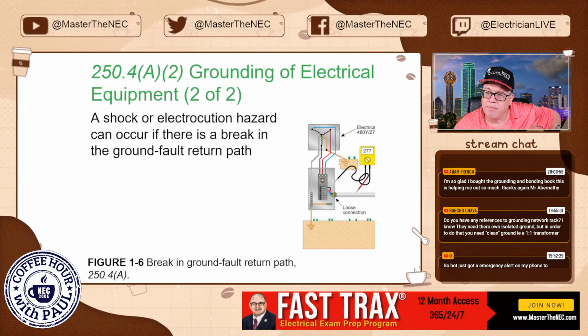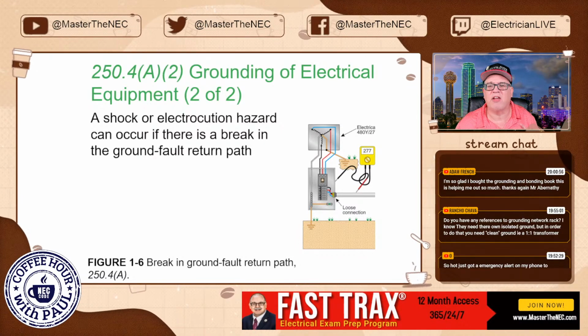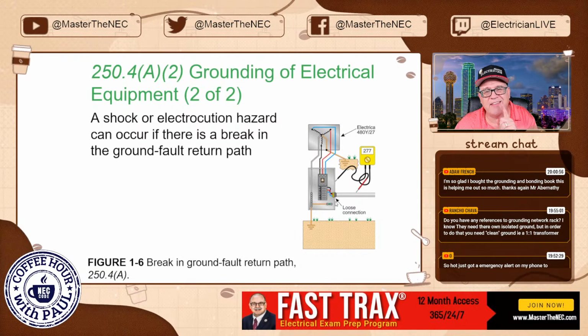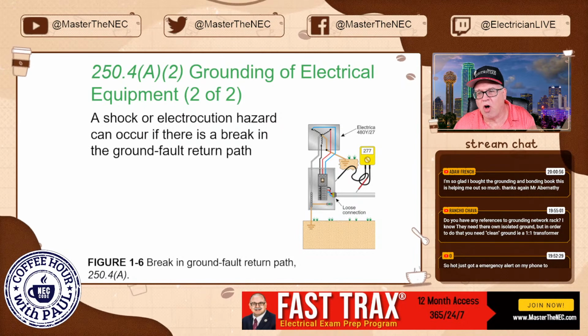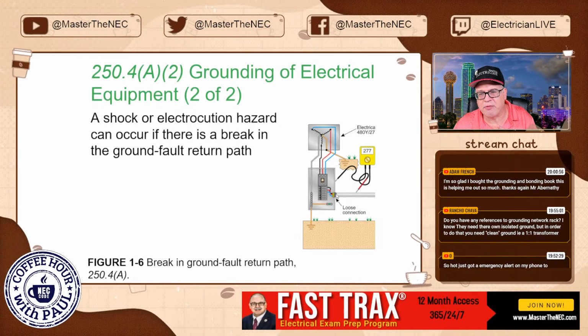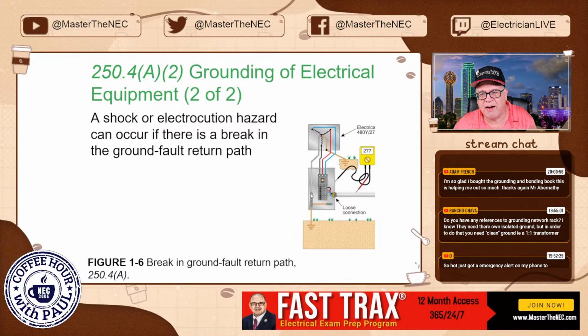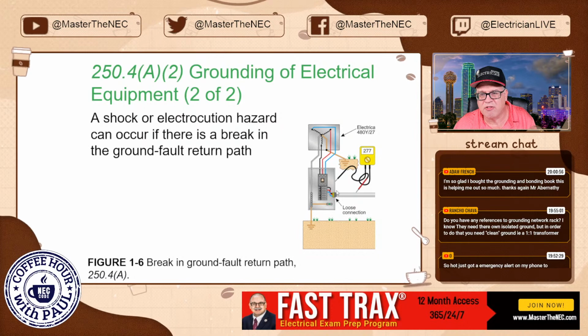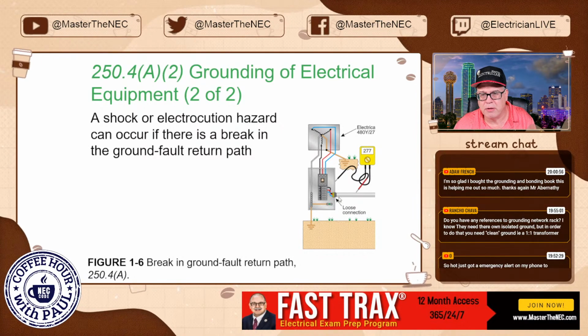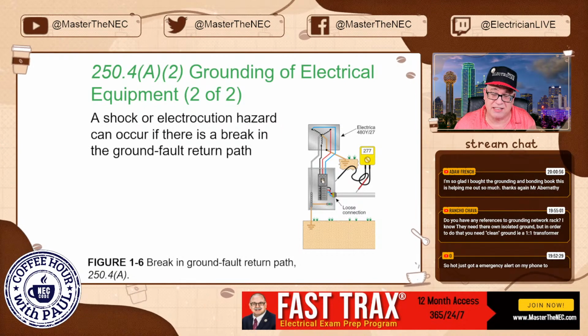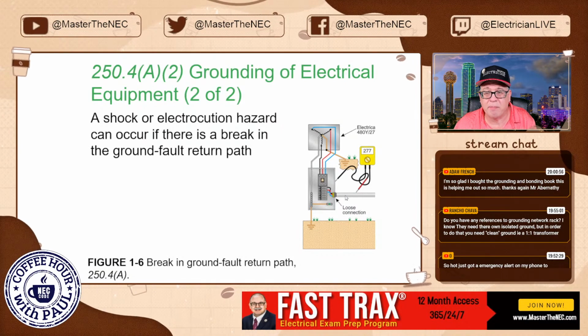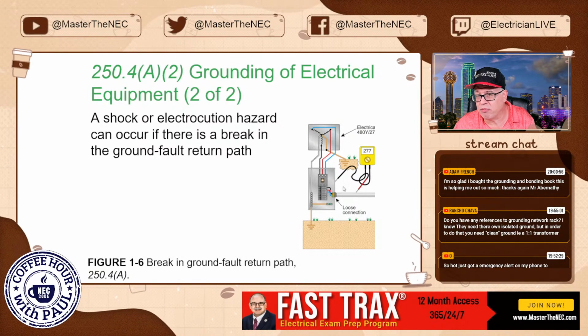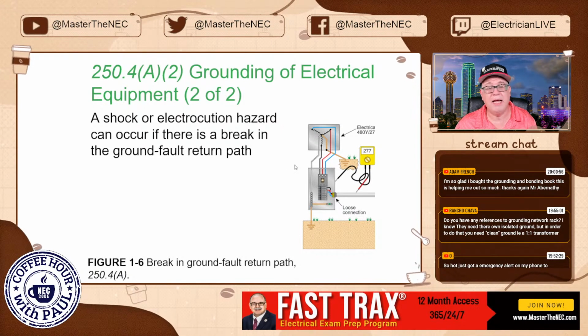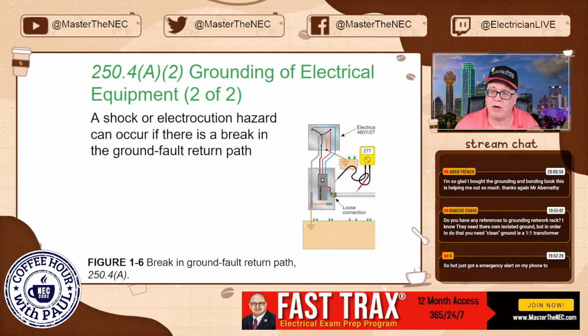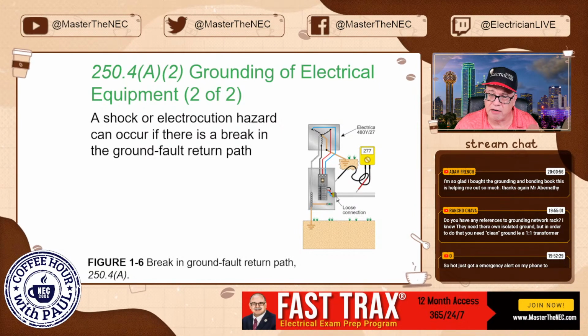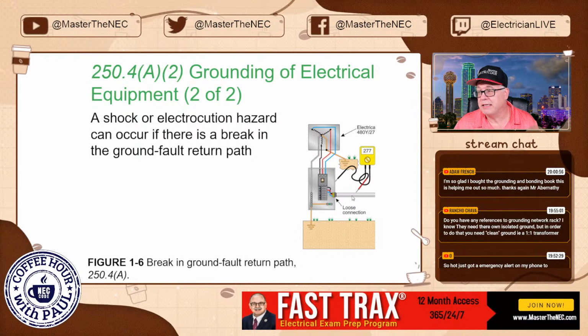And so there's a fault right here. As that fault current tries to get back and has a low impedance effective ground fault current path, in this case it's hindered because of a loose connection. So all of this just stays energized. Basically it stops right here. Here's your ground reference, because everything is bonded here back to the source, but it's loose right where it says loose connection. So I'm measuring between the box, which is connected to ground, and this raceway, which is basically floating. I'm measuring voltage across it, and I am going to have current crossing depending on how good this connection is or isn't, because you could see arcing right here.